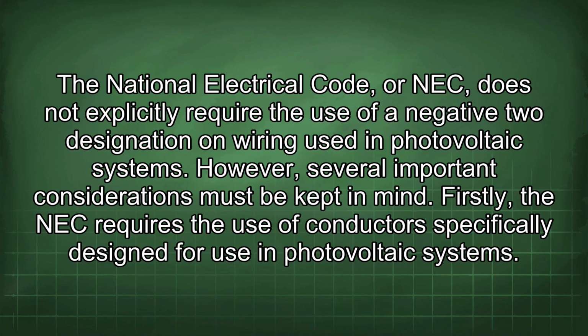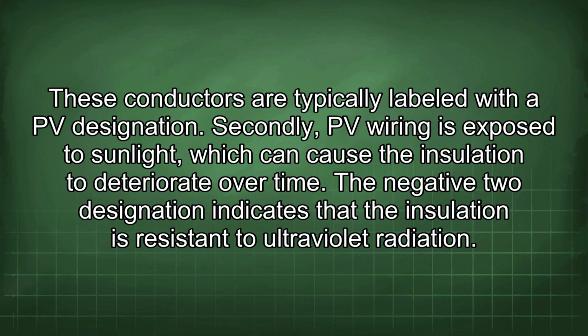The National Electrical Code, or NEC, does not explicitly require the use of a -2 designation on wiring used in photovoltaic systems. However, several important considerations must be kept in mind. Firstly, the NEC requires the use of conductors specifically designed for use in photovoltaic systems. These conductors are typically labeled with a PV designation.